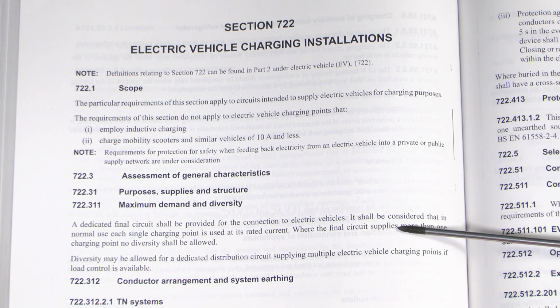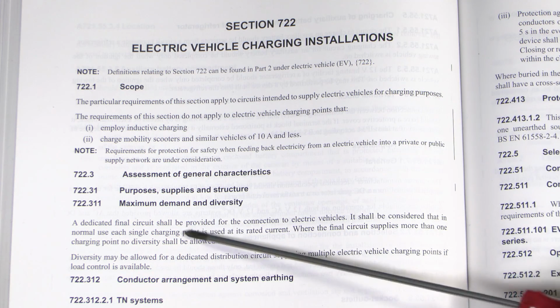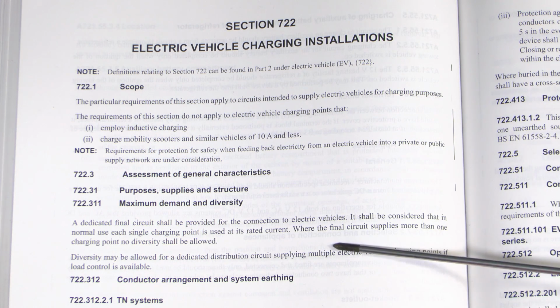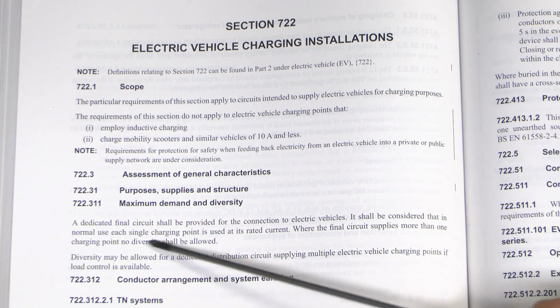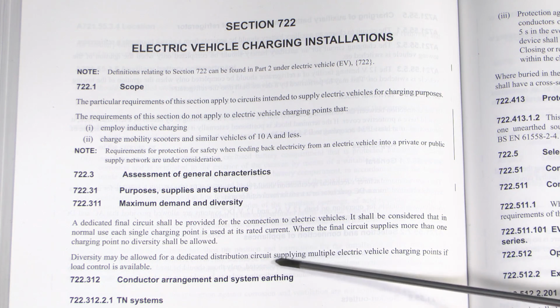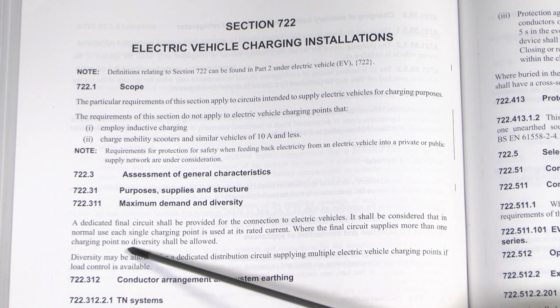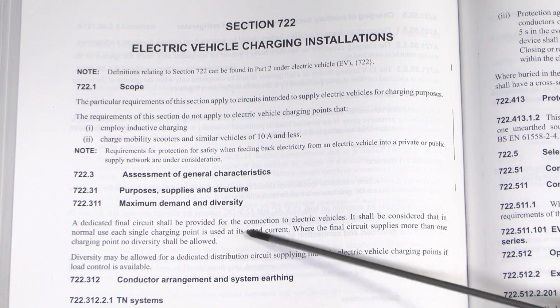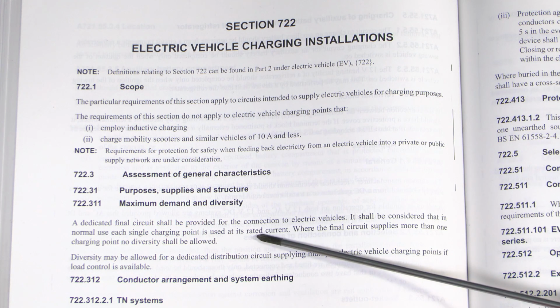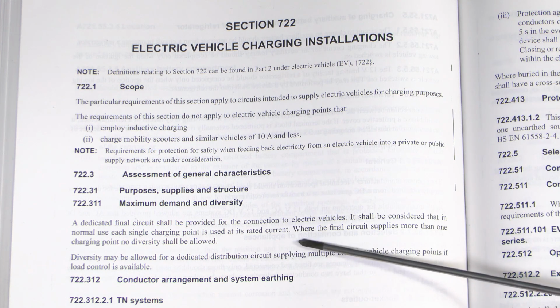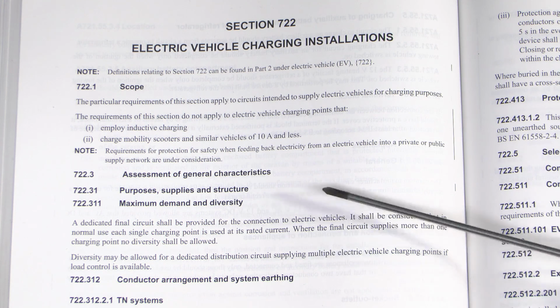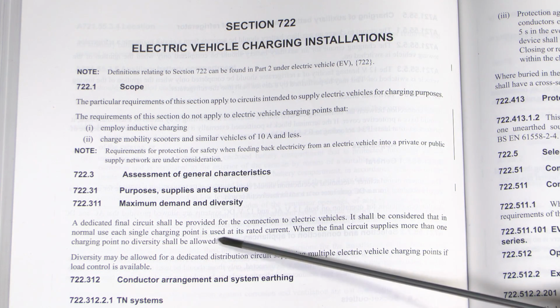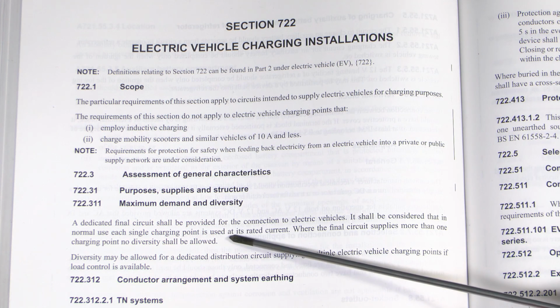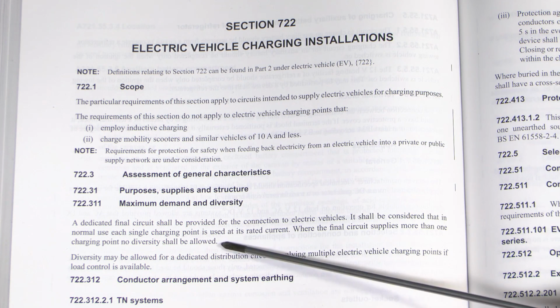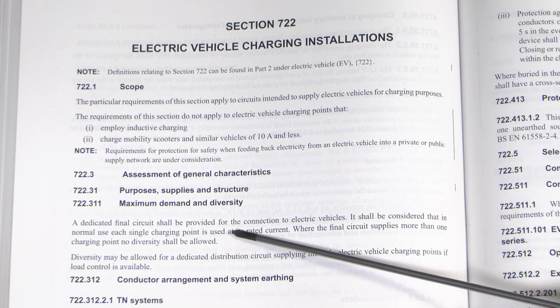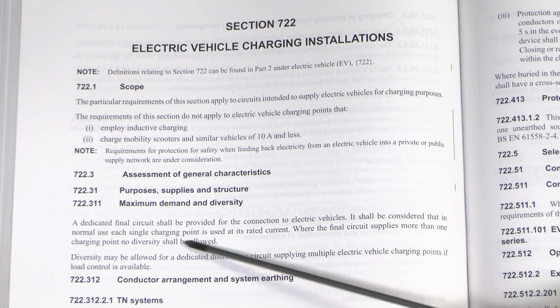And if we look down the bottom here, it says that a dedicated final circuit shall be provided for the connection to electric vehicles. It shall be considered that in normal use, each single charging point is used at its rated current, and where the circuit supplies more than one charging point, no diversity shall be allowed. Now this is important because if you're going to install, say, a 32 amp circuit for a charging unit, which is probably the most common one for domestic installations, then when the vehicle is plugged in, it's going to pretty much use all of the current that's available, which is going to be in the 32 amps range. And whilst the vehicle's charging, of course, it's going to use that current all the time at the full rate. So again, no diversity is permitted.